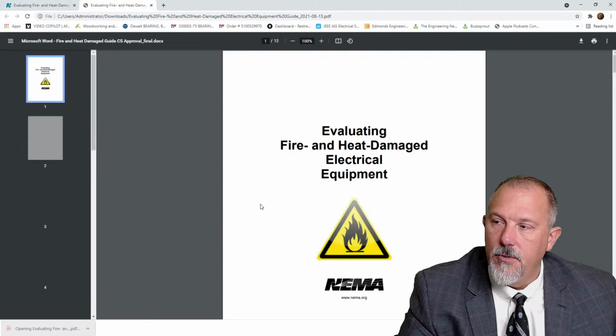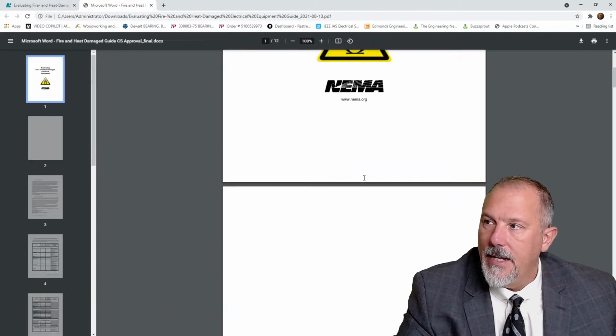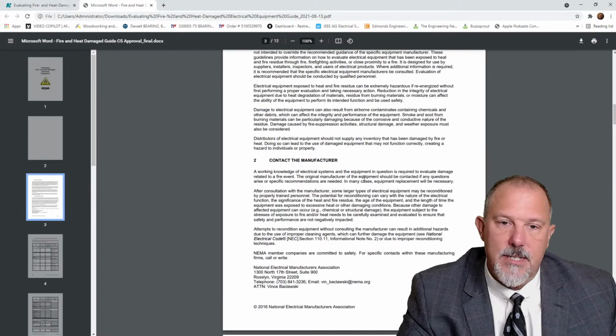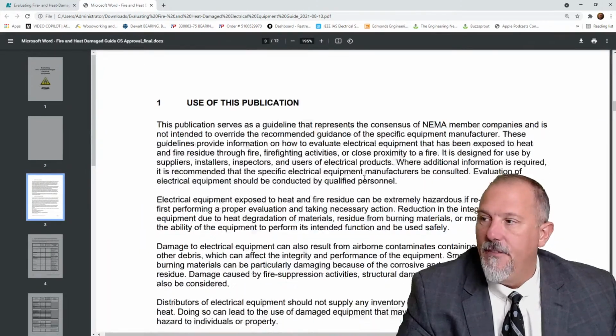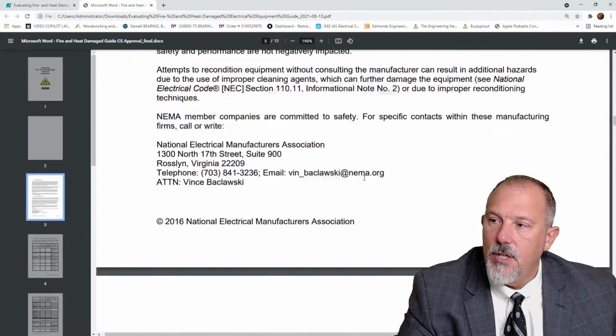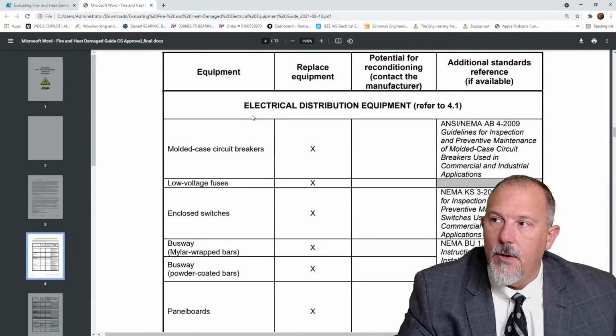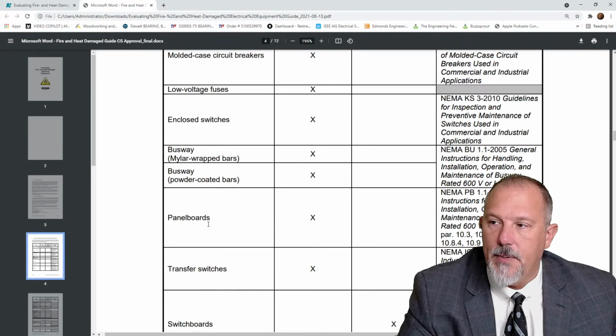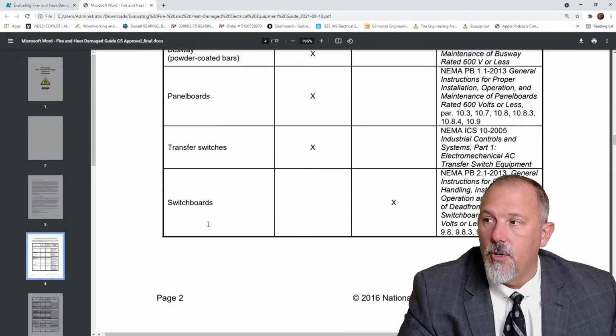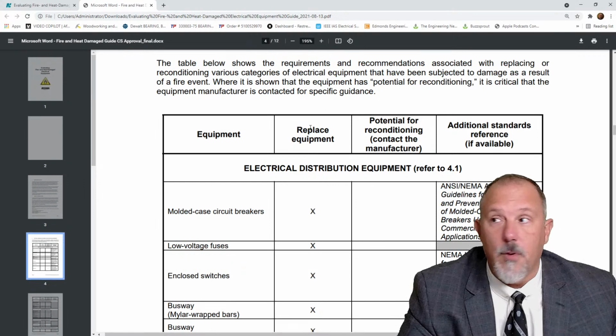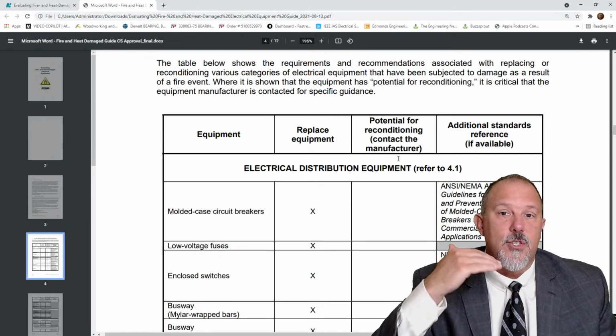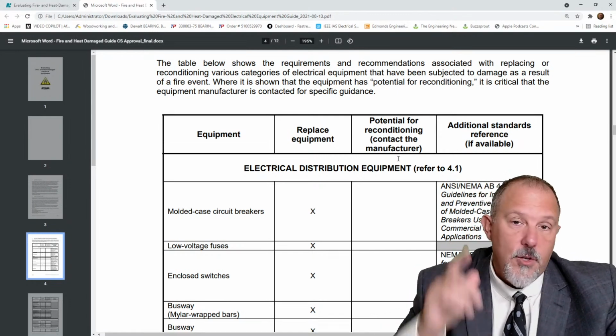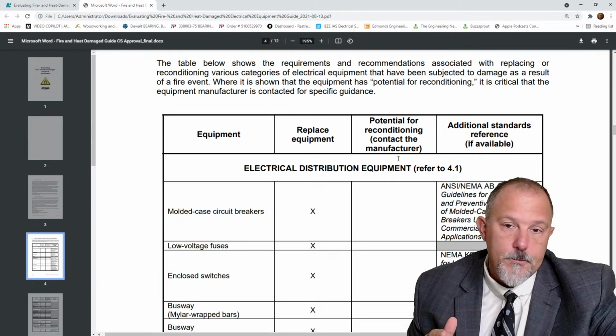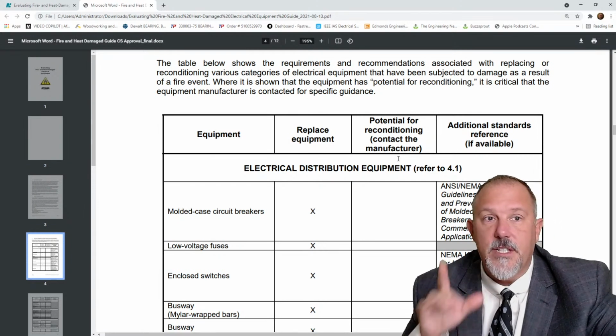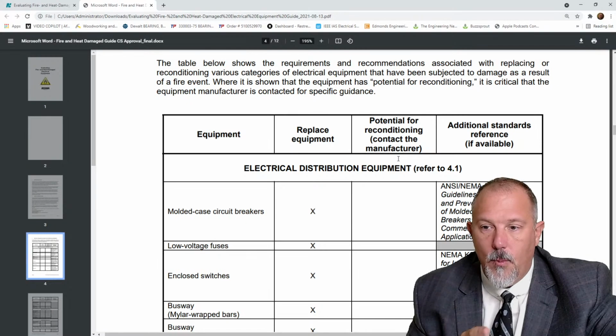And once you download it, it talks about fire and heat damage. So it doesn't necessarily mean that the equipment was in a fire, but it speaks to all the different types of equipment: enclosed switches, busway, panel boards, transfer switch, switchboards, etc., on whether or not you should replace the equipment or you can recondition it. So this is a great reference to answer his specific question. Use this reference to point to and read through it. It's a free download off of the NEMA website.